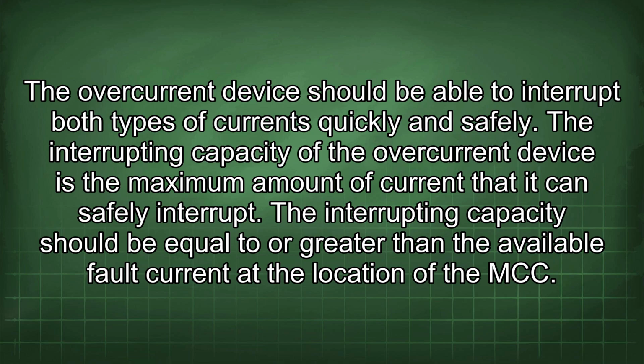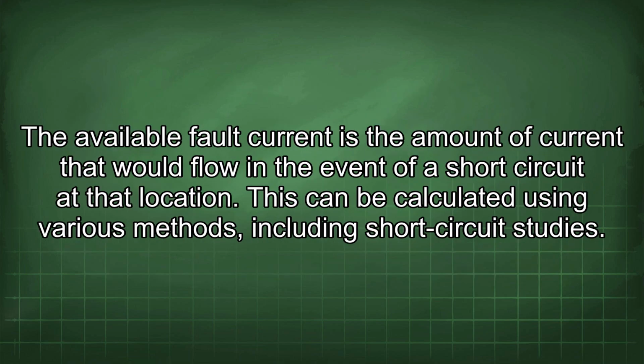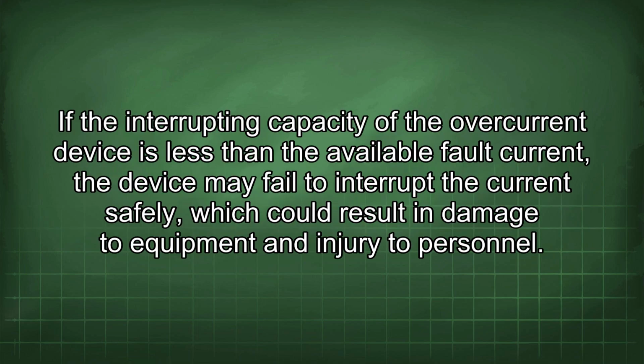The interrupting capacity of the overcurrent device is the maximum amount of current that it can safely interrupt. The interrupting capacity should be equal to or greater than the available fault current at the location of the MCC. The available fault current is the amount of current that would flow in the event of a short circuit at that location. This can be calculated using various methods, including short circuit studies. If the interrupting capacity of the overcurrent device is less than the available fault current, the device may fail to interrupt the current safely, which could result in damage to equipment and injury to personnel.